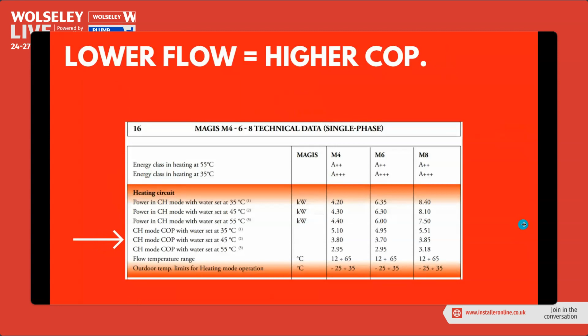But as we raise that flow temperature that we require for the property, the COP starts slipping away. As we said earlier, we have to have a COP of 3 or above to necessarily beat a gas boiler. So this is where hybrid technology is really clever, because we can use our heat pump when we need a lower flow temperature, and then when we actually need a high temperature, we can use our gas boiler, so we can make it more efficient.